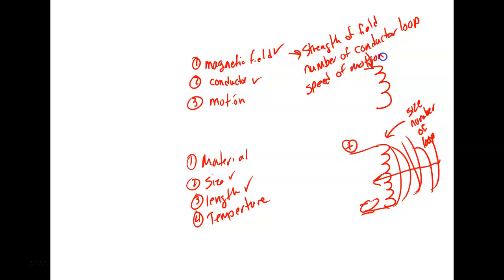So the problem we have with DC coils, DC relays, or even DC solenoids, is that when you turn this thing off, this magnetic field comes collapsing back into that, and we got a lot of turns of wire, and it induces a high voltage back into that thing. Now, there's not much current available to it, but the voltage is so high. One of the ratings on all electronic devices is called the breakover voltage. If you exceed the breakover voltage of a solid state device, it will be damaged. Now, the problem is it built out this way, so when it collapses back, it generates what we call a counter EMF.